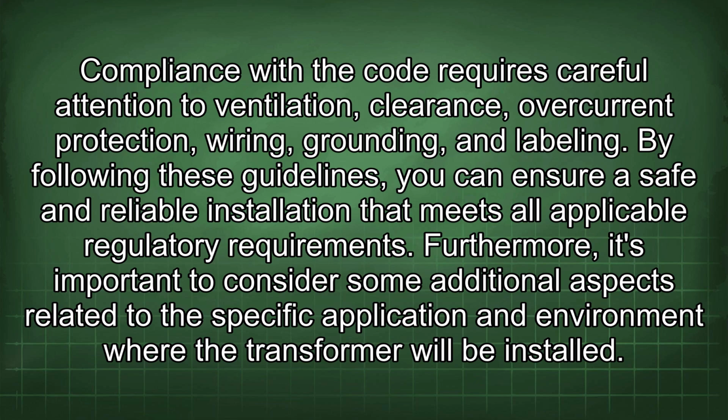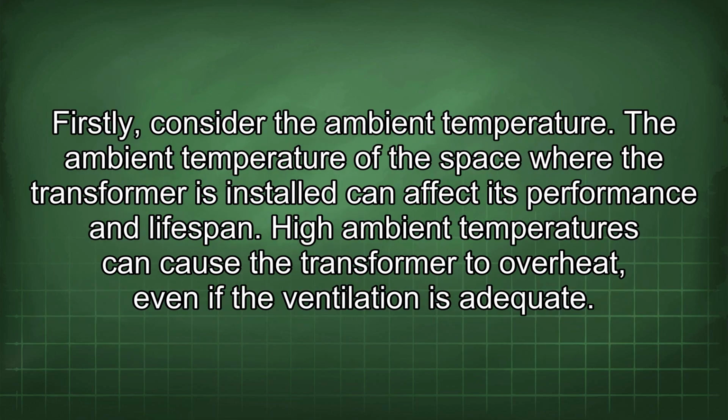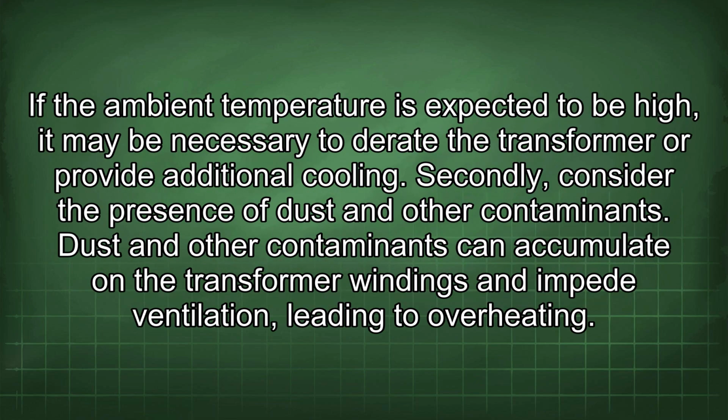Furthermore, it's important to consider some additional aspects related to the specific application and environment where the transformer will be installed. Firstly, consider the ambient temperature. The ambient temperature of the space where the transformer is installed can affect its performance and lifespan. High ambient temperatures can cause the transformer to overheat, even if the ventilation is adequate. If the ambient temperature is expected to be high, it may be necessary to derate the transformer or provide additional cooling.